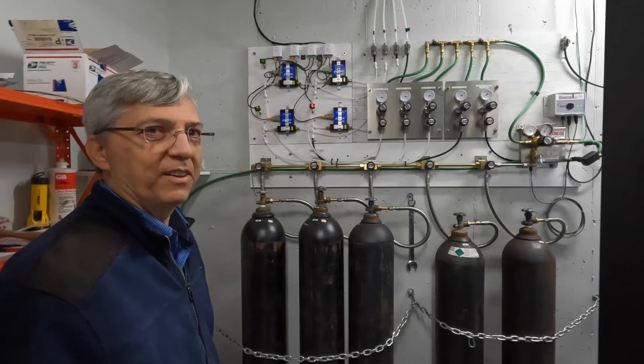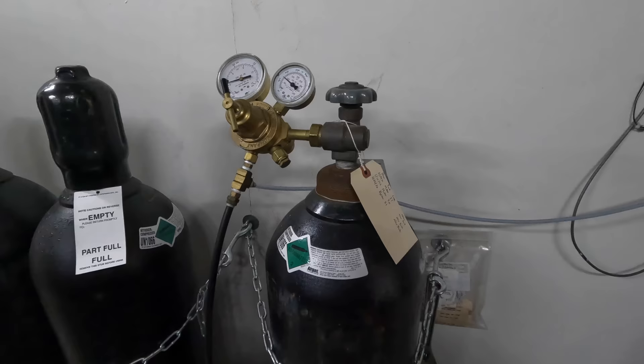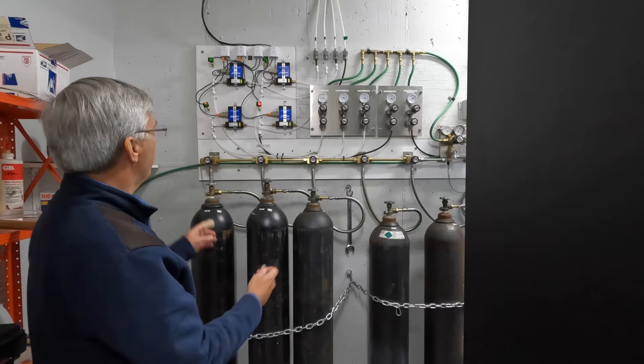You mentioned there's air inside the giant coax tube — but you need dry air. That's what the nitrogen is for. These are all nitrogen tanks, and because there's so much line and it's so big, we have multiple tanks backing each other up. Everything is monitored.